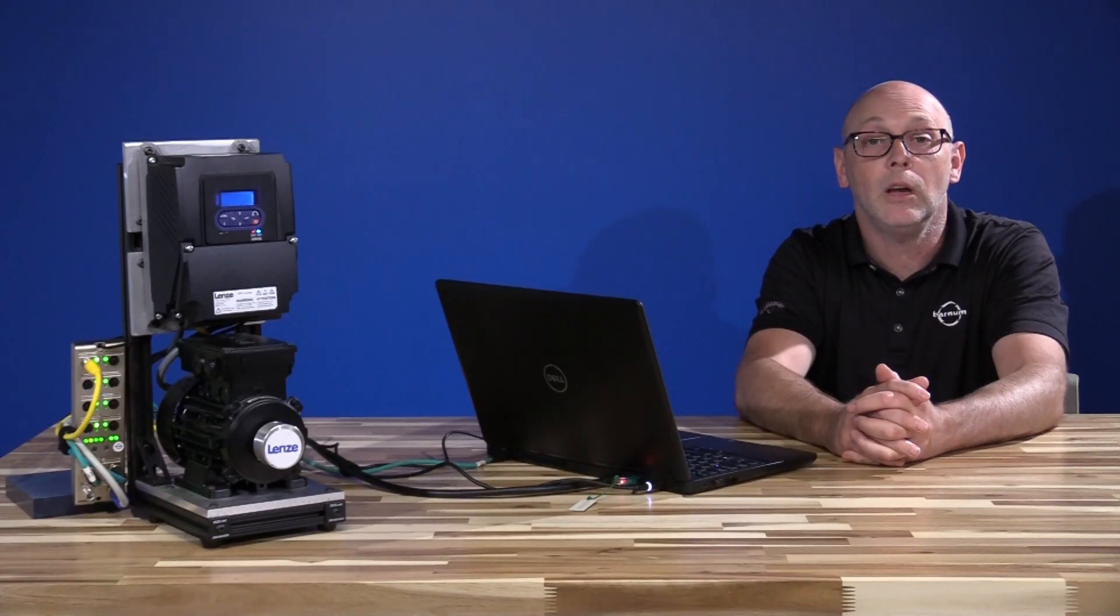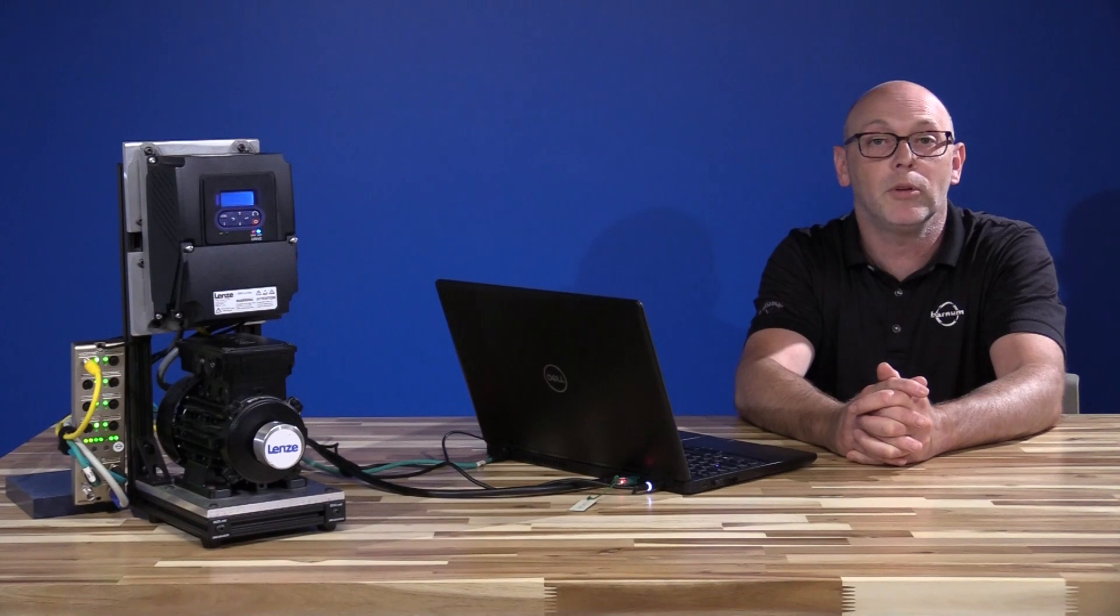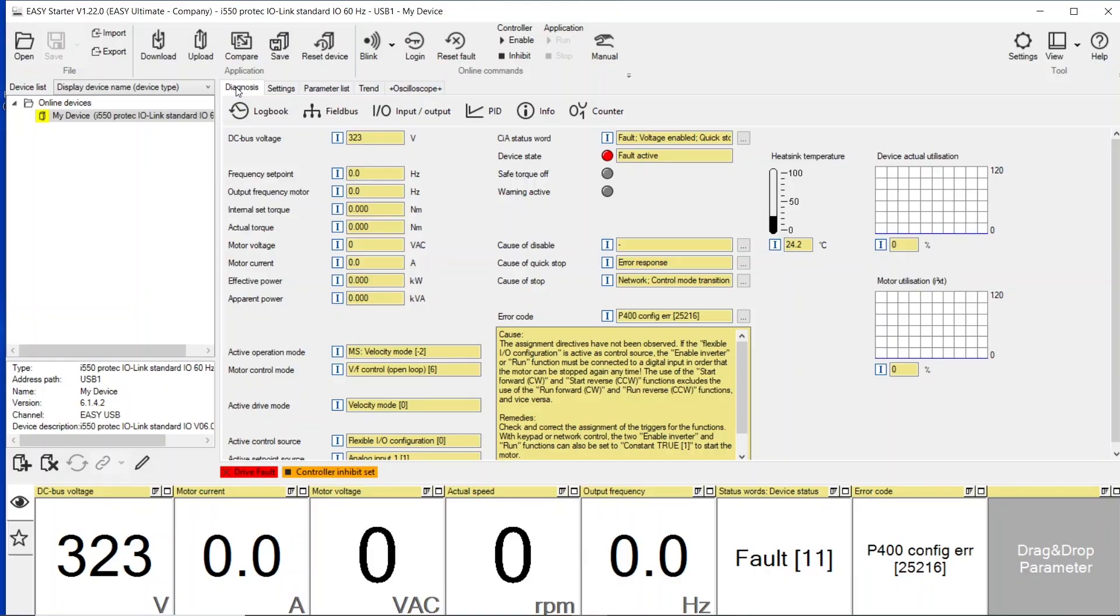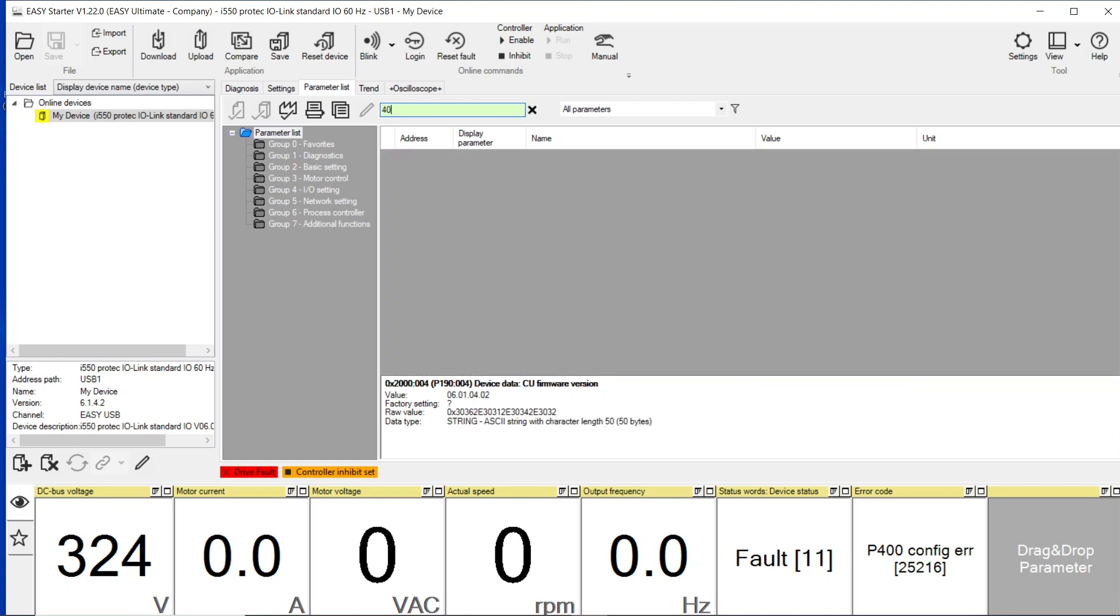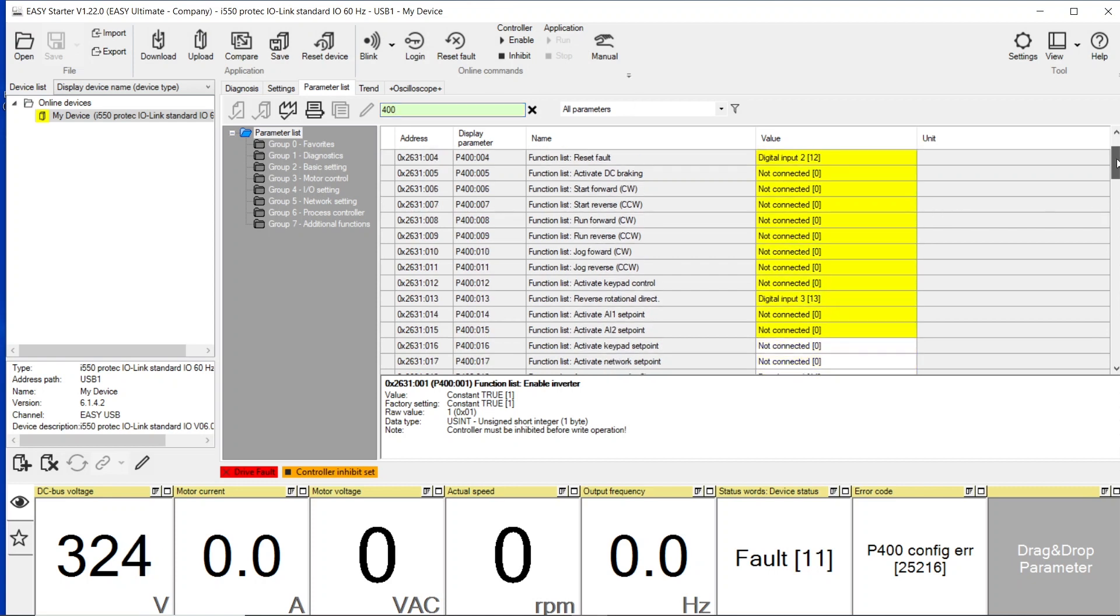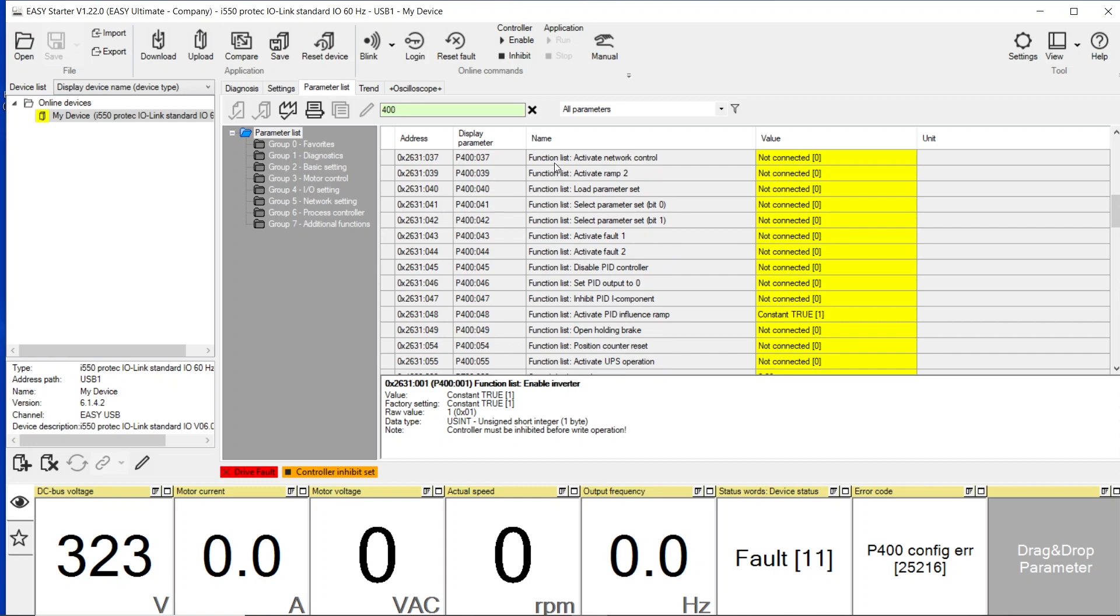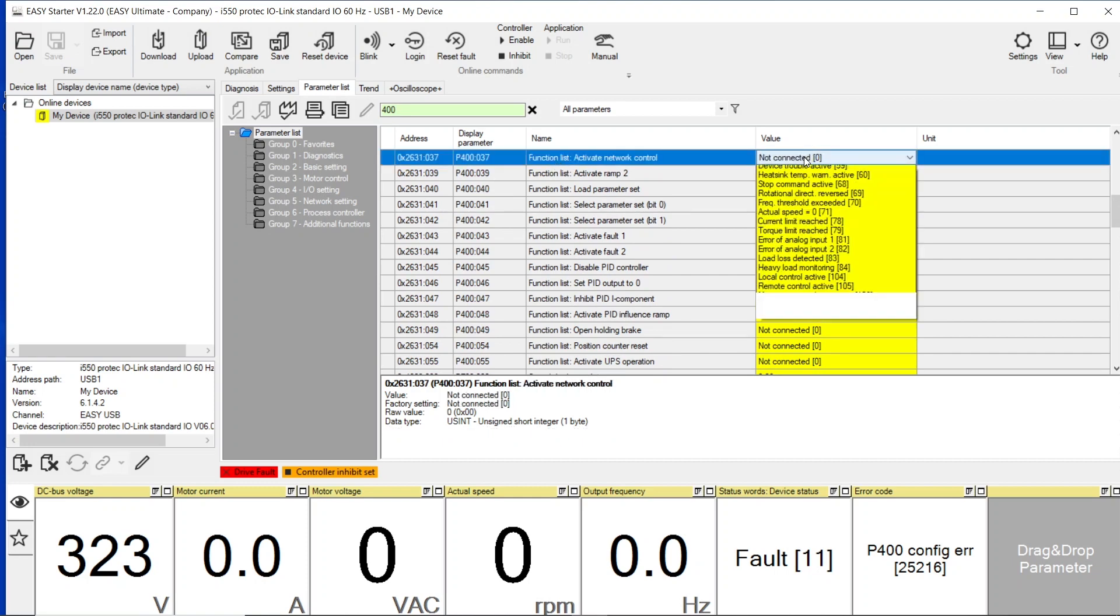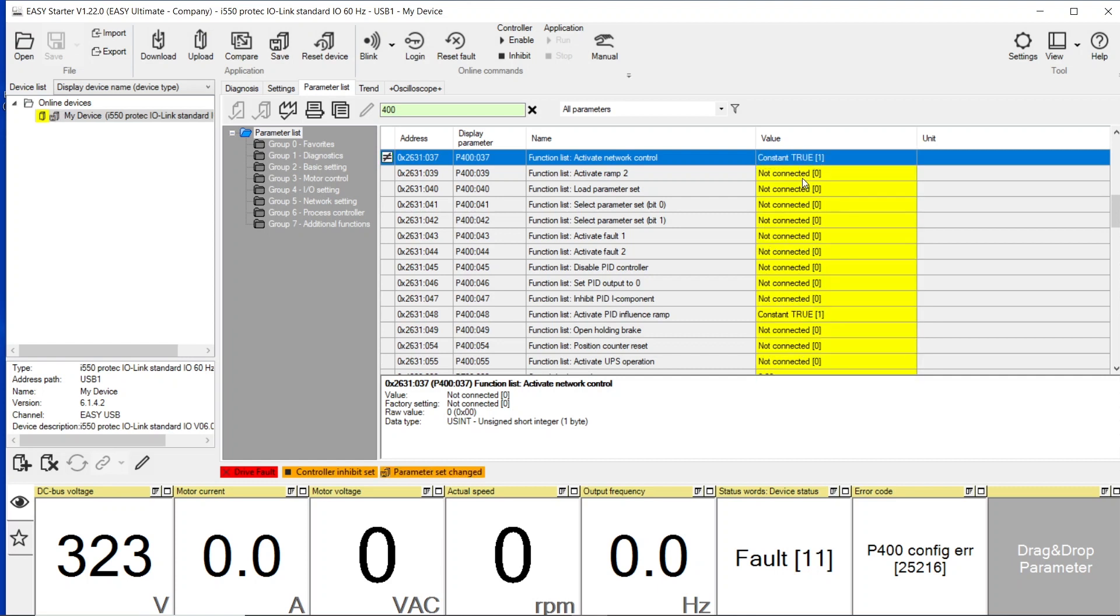Once you're in the software, there are really only two parameters that need to be set. To do that, you're going to go to the parameters list here right in the center. We are going to type in 400. We are looking for parameter 400:037. This is where we're going to activate network controls. We're going to go from Not Connected, use the drop down, and go to Constant TRUE.